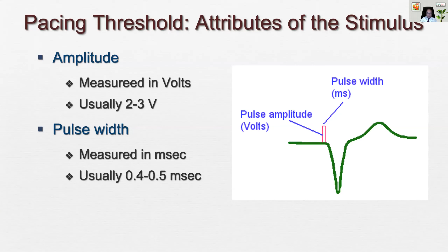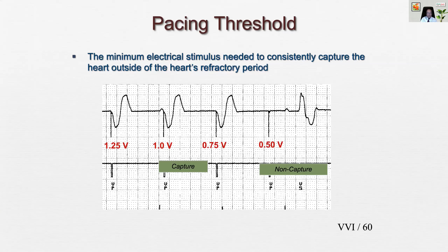The threshold test is performed like this: we keep on decreasing the pacemaker voltage output. Here you can see that 1.25 volts is capturing. Then we decrease it to 1 volt, which also captures. Then we decrease it to 0.75 volt, which also captures. Then we decrease it to 0.5 volt, and that loses capture. So the threshold is the last captured voltage. In this example, the patient has a pacing threshold of 0.75 volts. We usually program it to twice the captured voltage if we are doing manual programming. But in automatic systems, it can save battery significantly.